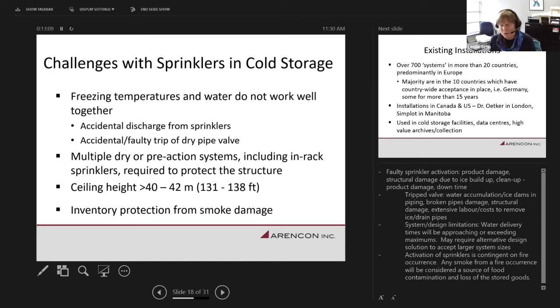With the high ceiling heights, we also have challenges that we haven't had fire protection systems tested or sprinklers listed up to these heights. So we end up with more in-racks, or we tend to be leaning towards alternative solutions anyways. The added bonus with any fire prevention system, even early warning smoke detection, is that if you can get to a fire or prevent it from growing, you're going to limit the smoke damage. By the time a sprinkler system operates, there's going to be smoke damage, and the commodities are basically slated for destruction. There's no recovery at that.